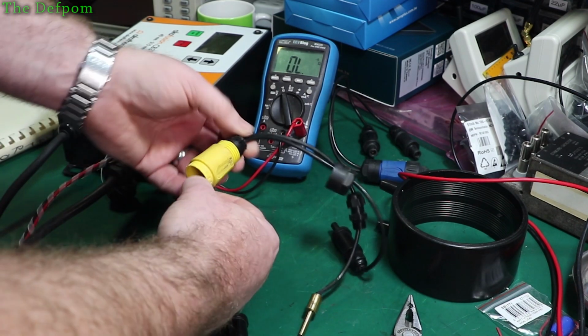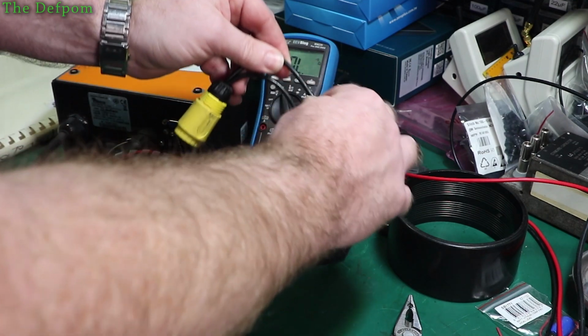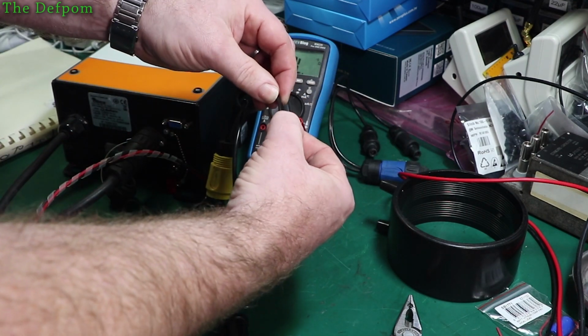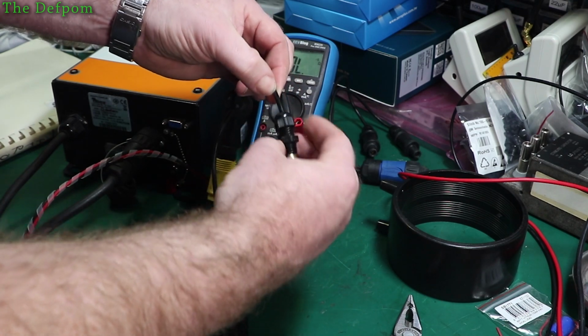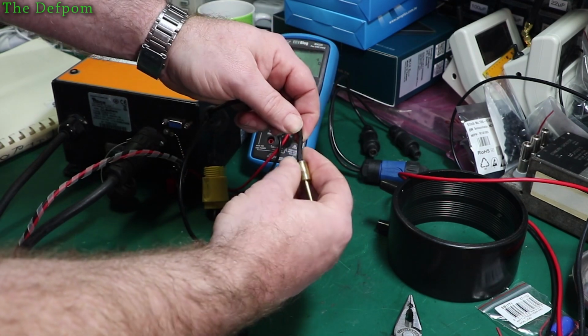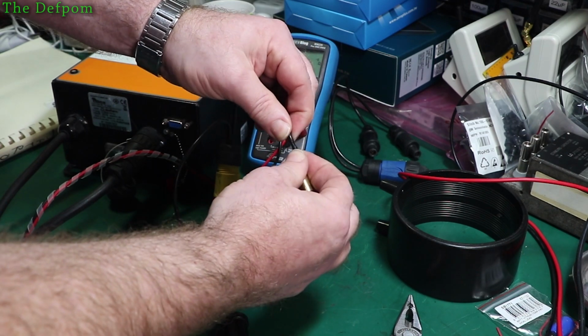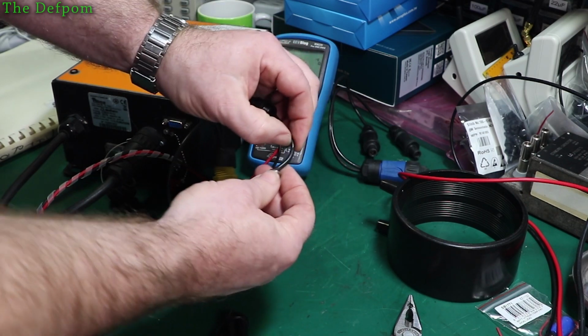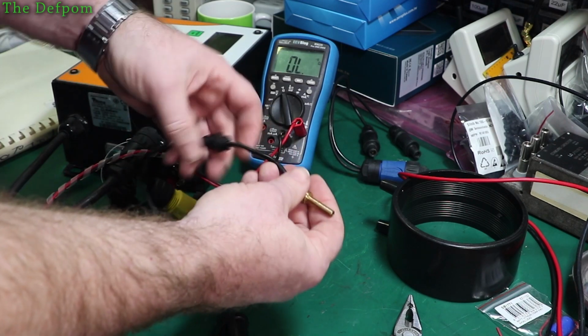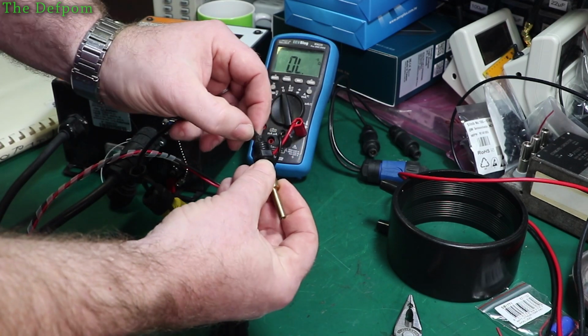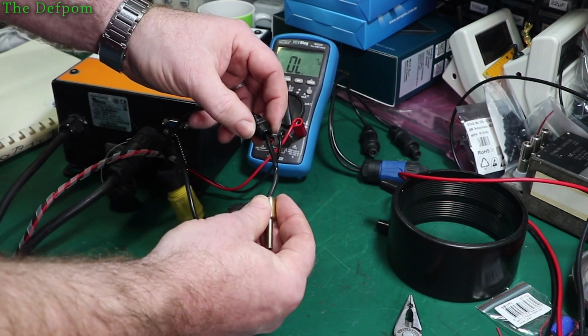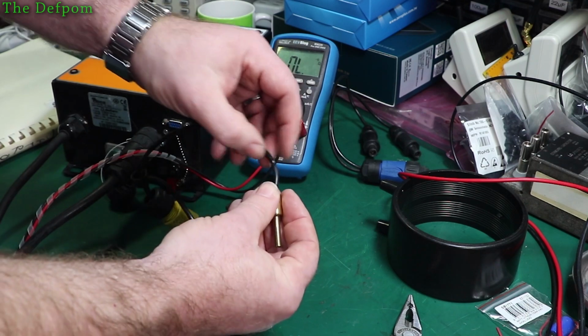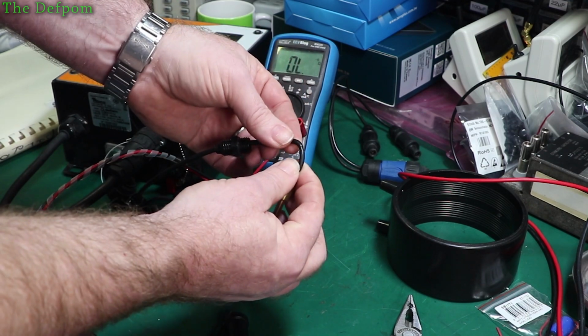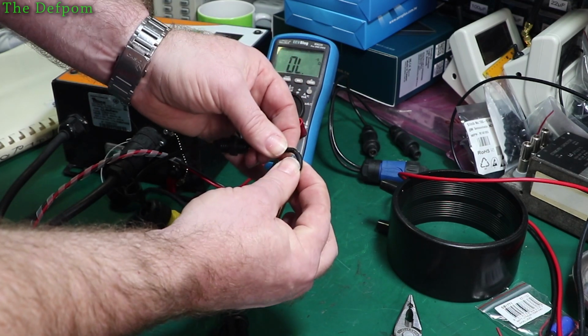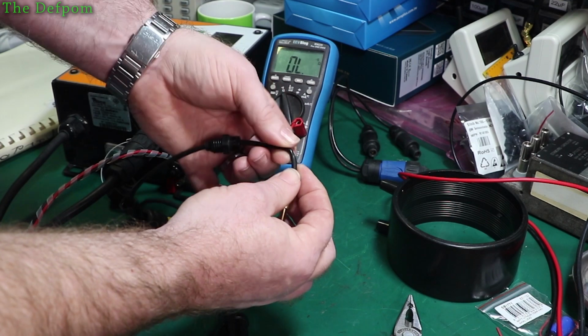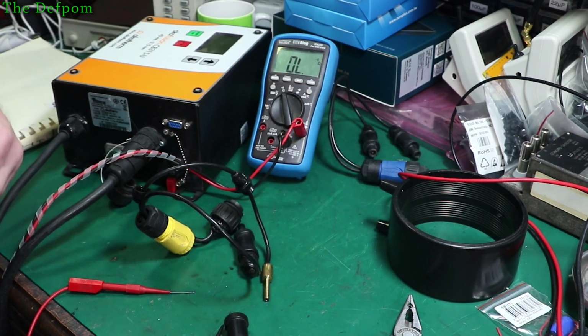So there must be a break in that wire somewhere, which is really interesting. There's little nicks on it just here. Just looking for any signs of being compressed. I mean, obviously here where the gland is, but I don't know, maybe. That feels stiffer here. See this little bit here, which is sucked in? It's about there. That's okay, that's where the gland was. But it feels stiff there. And normally when you get a stiff bit, it usually means that it's got hot and partially welded itself. Maybe. I could be wrong.